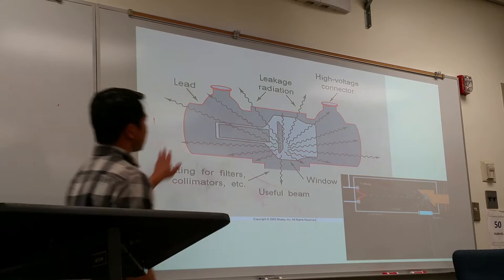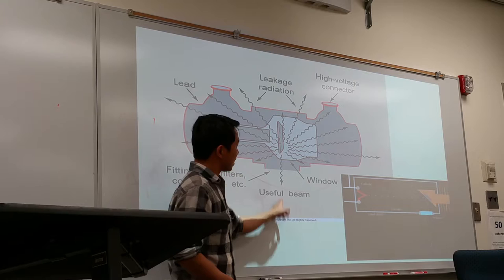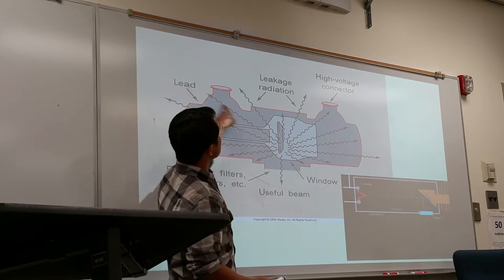Here is a diagram of the metal housing with the x-ray tube inside. The only point where the useful x-ray beam should come out is the port, where it interacts with the patient. Any place where x-rays are coming out beyond that port would be considered leakage radiation.